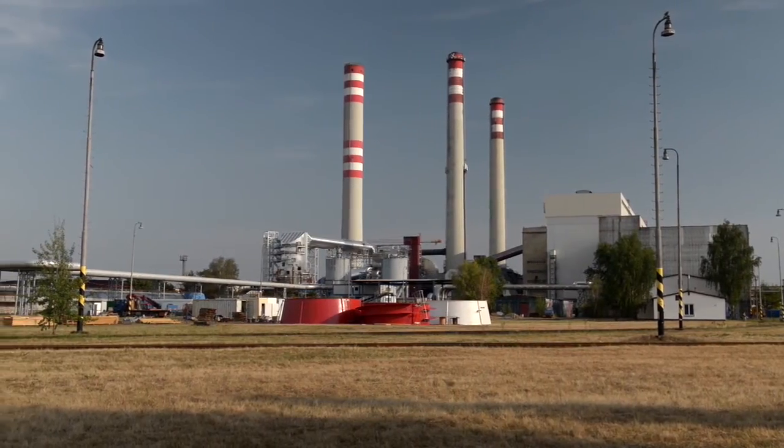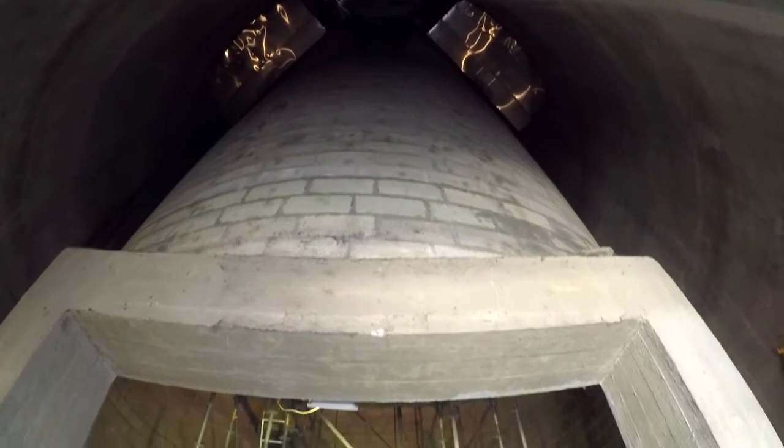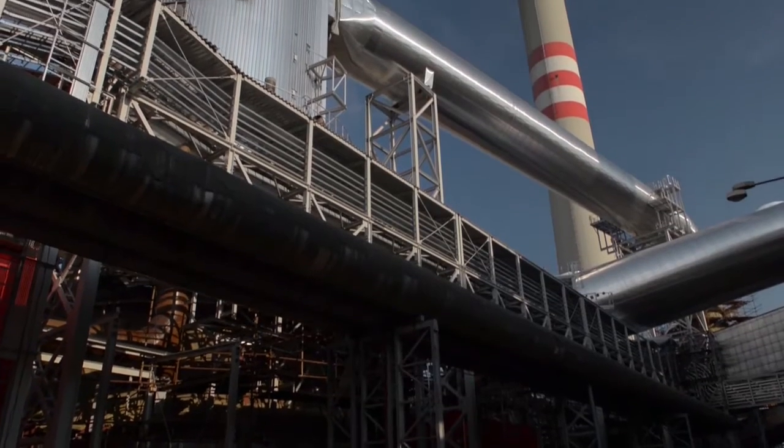The Opatovice power plant chimney is a brick chimney, which is generally unfavorable for wet operation. This is primarily because any liquid collected on the inside of the liner can seep through to the outside, which could lead to structural problems with the chimney.